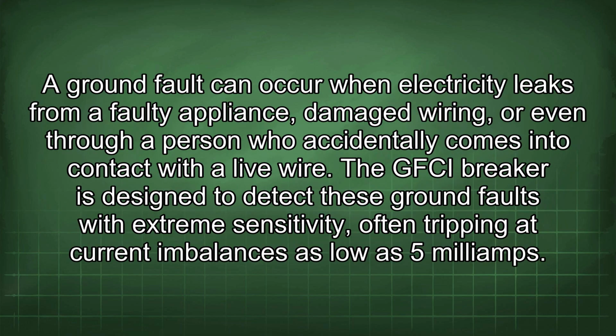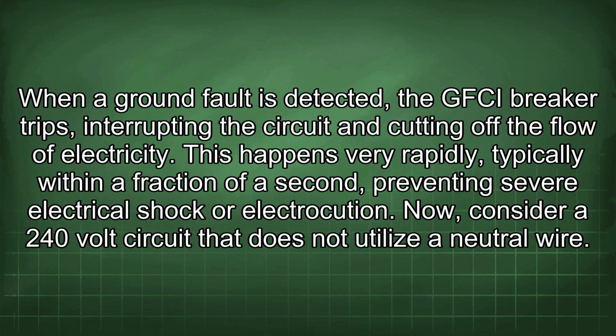A ground fault can occur when electricity leaks from a faulty appliance, damaged wiring, or even through a person who accidentally comes into contact with a live wire. The GFCI breaker is designed to detect these ground faults with extreme sensitivity, often tripping at current imbalances as low as 5 mA. When a ground fault is detected, the GFCI breaker trips, interrupting the circuit and cutting off the flow of electricity. This happens very rapidly, typically within a fraction of a second, preventing severe electrical shock or electrocution.